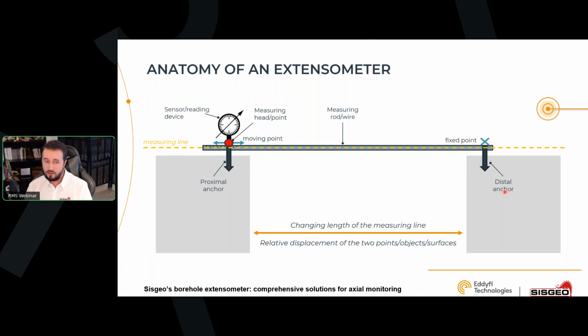1 point would be the distal anchor. So it's not exactly a fixed point, but it can be a fixed point. So this distal anchor is linked to a measuring rod or a wire. So the movement of this point is transmitted completely through this measuring rod. Then what you measure here is not the full distance, but you measure only here the change, the movement, the local movement between the proximal anchor here and the rod, which is linked to the distal anchor. You measure this through the measuring head or the measuring point, through a sensor or readout device. So this is the main principle that you have to keep in mind.